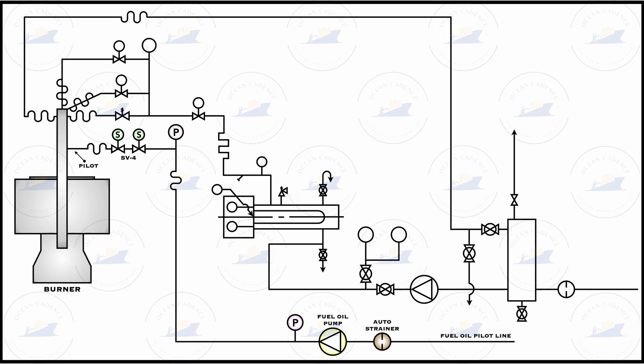After that we have a main burner supply line. For this main burner supply line we can use either diesel or VLSFO as per the area we are sailing in, and the elements in the line would be arranged accordingly. We would have a separate fuel oil pump, a heater used when running on VLSFO — since VLSFO has a higher viscosity it needs to be maintained at a higher temperature to ensure it burns in the main burner — separate pressure gauges, and separate solenoids for the level of firing and the firing sequence.